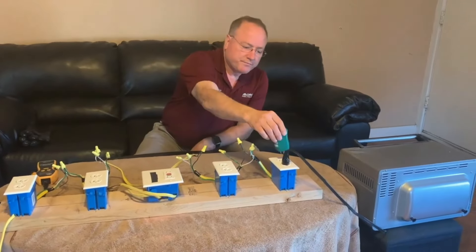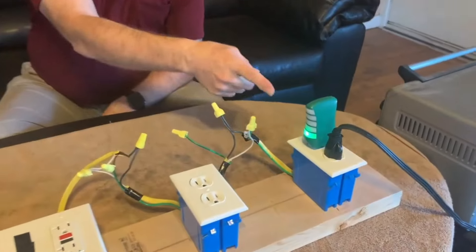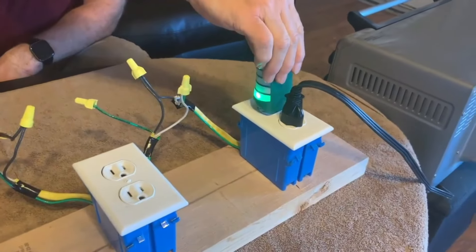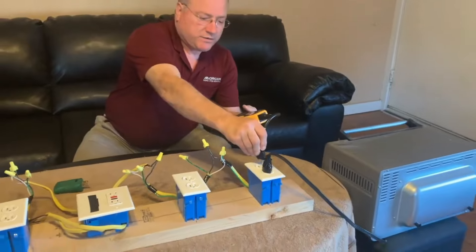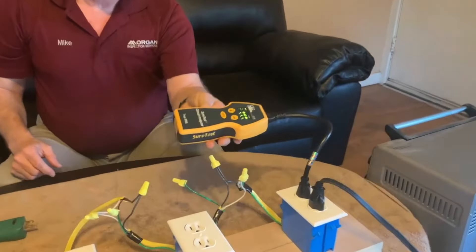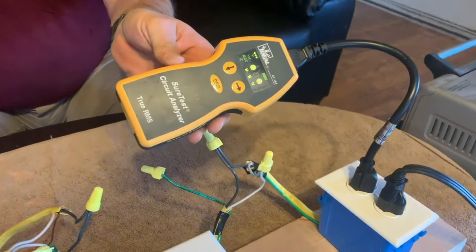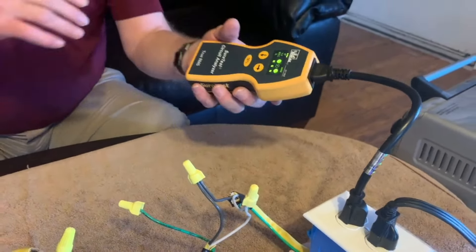So with a reverse polarity and a combination of false ground or bootleg ground, let me show you what you have. Again, this tester will show that everything's correct. You've got the green light. The SureTest circuit analyzer will also show, just like it did earlier, it'll show the flashing F for the false ground. So it is picking up that there's a problem.